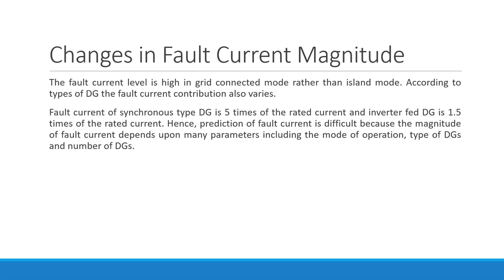Changes in fault current magnitude. The fault current level is high in grid connected mode rather than islanded mode. According to the types of distributed generators, the fault current contribution is also going to vary. If the distributed generation is different, your fault current will be different. Fault current of synchronous type DG is 5 times the rated current, and inverter fed DG is 1.5 times. See the changes, 5 times and 1.5 times of the rated current.